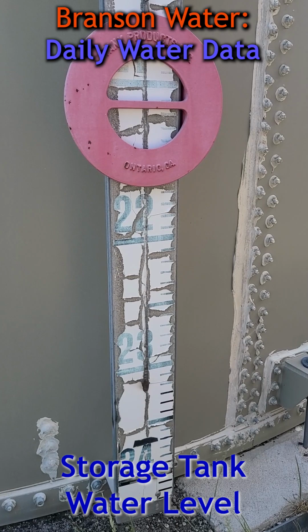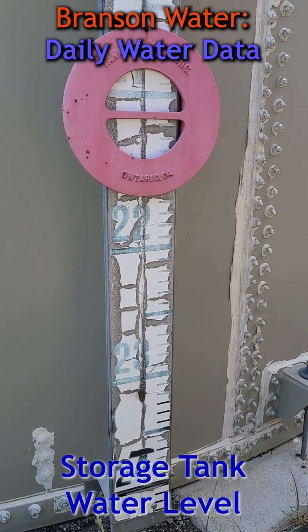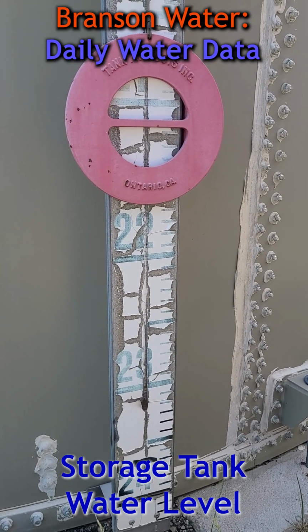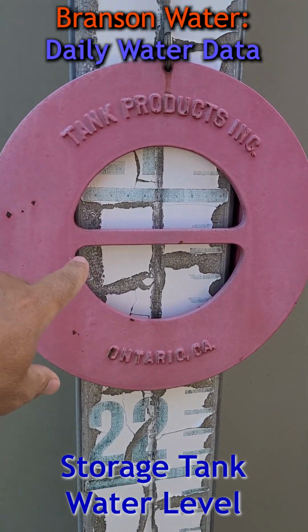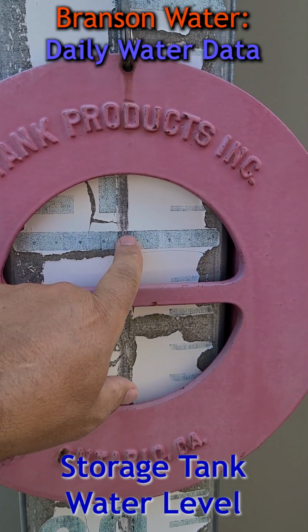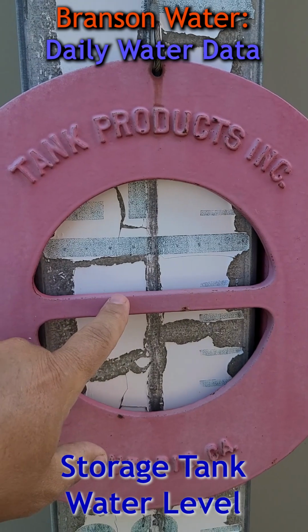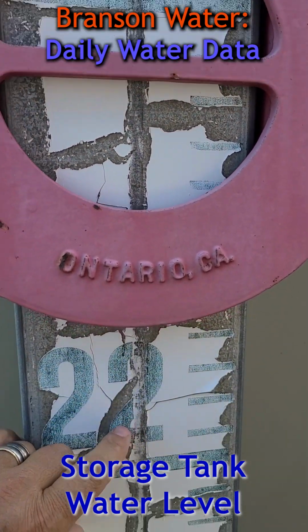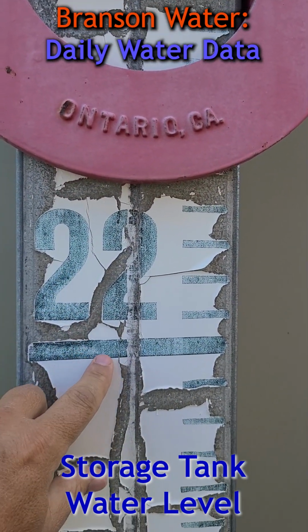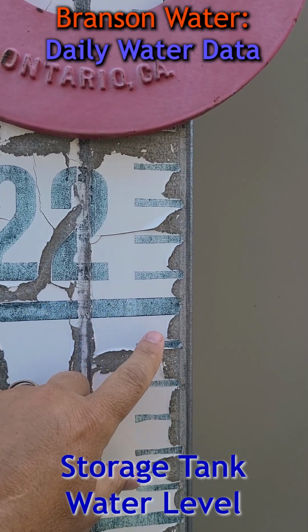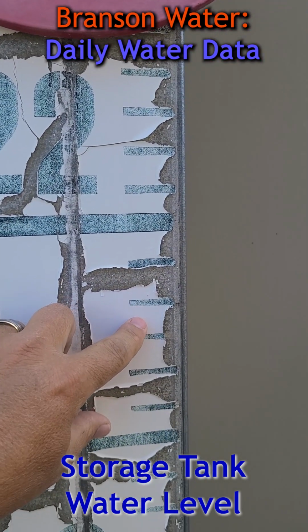One of the first things you will record is the water level in the storage tanks in feet. Now you're going to actually look at where this red line intersects these lines on this measuring stick. Let's talk about what those each represent. Here's the number 22. Right below it, that is 22 feet. Each of these little lines represents 1 inch.